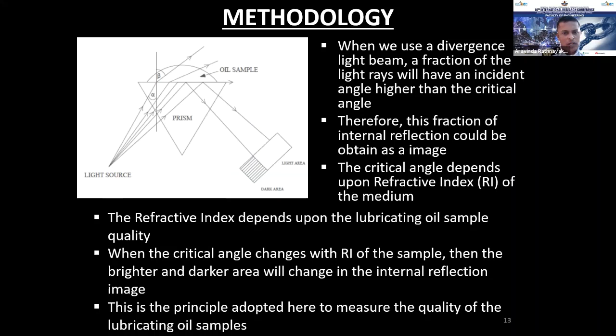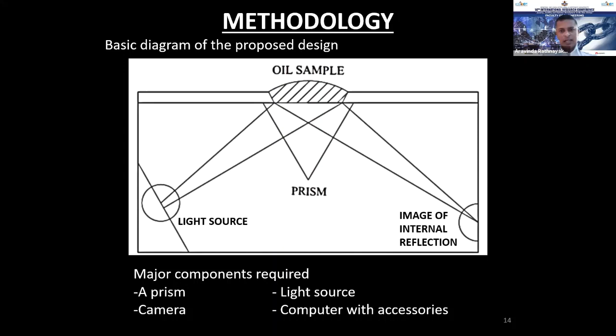The most important factor is that the critical angle of reflection depends on the refractive index of that particular medium. And the lubrication oil refractive index is dependent upon the quality of the lubrication oil. When the critical angle changes, the brighter and the darker region of this image will change. That is used to fabricate this lubrication oil analyzer. A basic schematic of the lubrication oil analyzer is shown on screen, but the major components used are a camera and a computer with accessories.